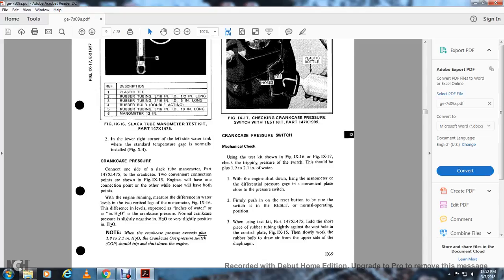Crankcase pressure: Connect one side of the slack tube manometer (part 147X1475) to the crankcase connection point shown in figure 9-15. The engine will have one or both test points. With the engine running, measure the difference between the levels of the two vertical legs on the manometer, figure 9-16. The difference in level, expressed in inches of water (H₂O), represents the crankcase pressure. Normal crankcase pressure is slightly negative to slightly positive in H₂O. When crankcase pressure exceeds +1.9 to +2.1 inches of H₂O, the crankcase overpressure switch should trip and shut down the engine.